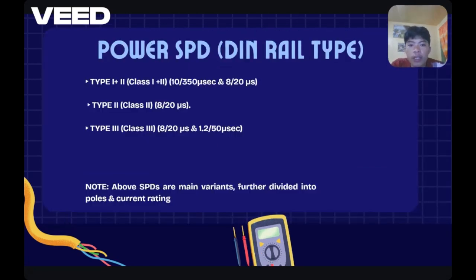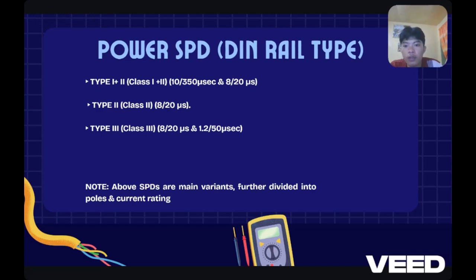Power SPD in DIN rail type, we have type 1 plus 2, with 10 over 350 microseconds and 8 over 20 microseconds. And type 2, we have 8 over 20 microseconds. And type 3, 8 over 20 microseconds and 1.2 over 50 microseconds. Note that the above SPDs are main variants and are further divided into poles and current rating.